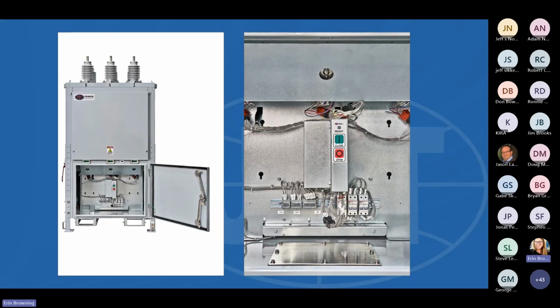Another close-up picture of the breaker low voltage cabinet. Again, there's not a lot going on in here. What we do see right in the middle is the controller. This is the brains of the circuit breaker. There's a capacitor in this larger rectangle piece right here. And then the smaller piece on the right is a printed circuit board. And the interface to this controller is really as simple as these push buttons on the front that allow a local open and close operation. And then there's a ready light. That's what you see right here.